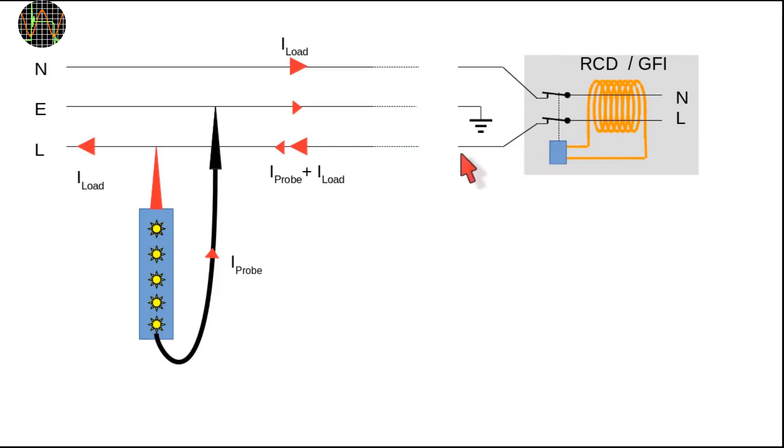When probing like this, there is now slightly more current flowing in the live wire. If that imbalance is larger than a few milliamps, it will trip the RCD. To minimize the measurement current and avoid nuisance tripping of RCDs, the probe uses battery-powered electronics for most of its functions and indicators, and the high-voltage warning LED is the only function with a low enough current that allows it to be powered from the probed circuit directly and stay below the RCD trigger threshold. The datasheet specifies this as less than 3.5 milliamps at 690 volts.